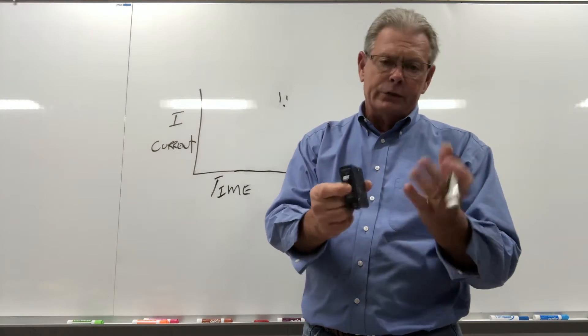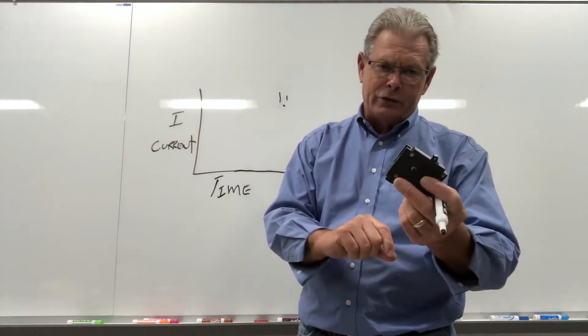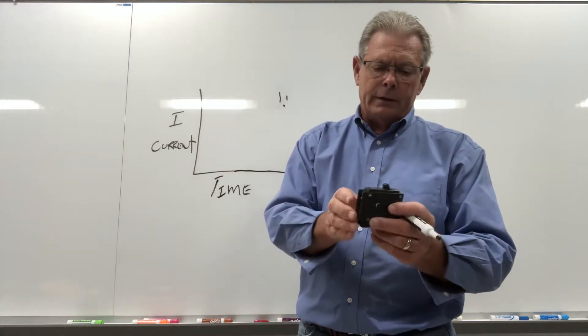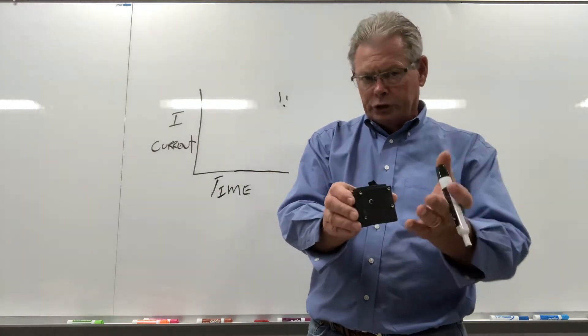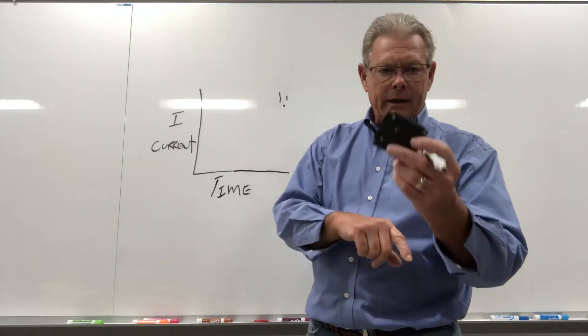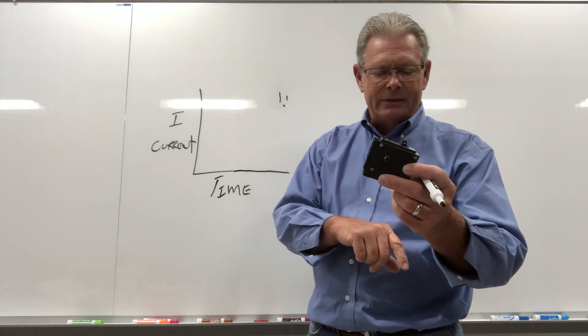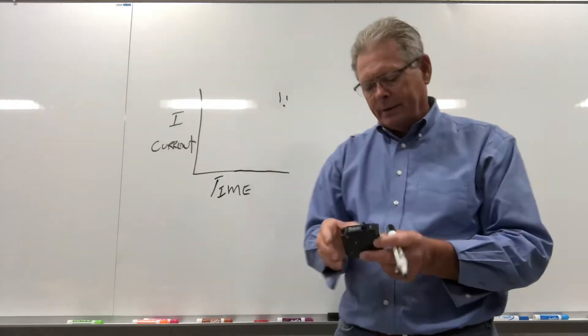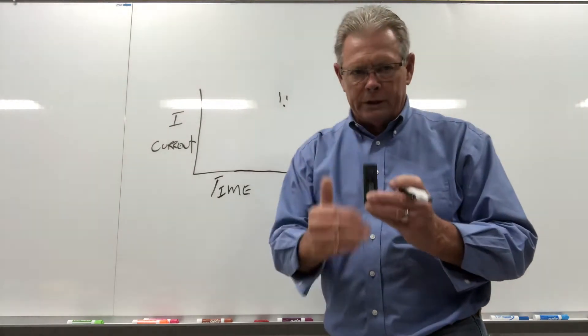So instead of this 15 amp breaker tripping at 15 amps, this thing might trip at 13 or 14. So even though it would be a loaded up circuit, 13 amps on a 15 amp breaker, it's okay until the outside heat gets to it. So outside heat can trip it. But let's talk about what normally trips these breakers.